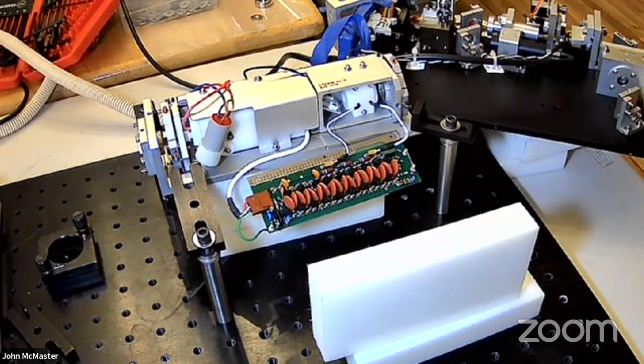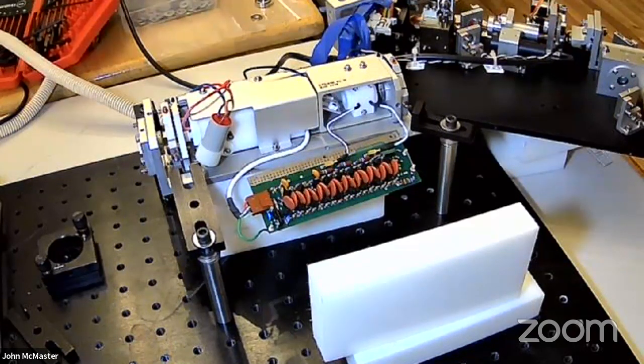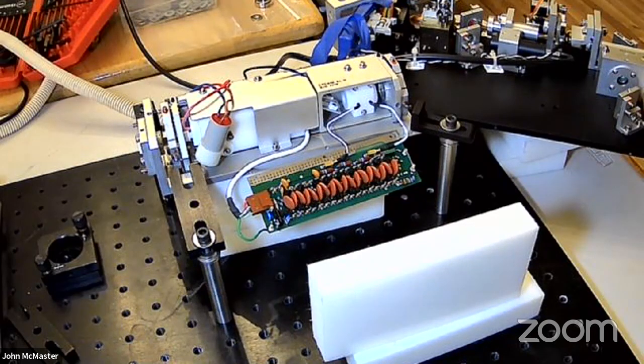Great. And so now the idea is if we were to just replace this one element, it's going to knock everything out of alignment. And there are so many optics in here that need to be aligned. It's going to be very hard to get everything, starting from that point, back to a working state. So it turns out to be easier to do this. Remember I said that we could operate this as just a very long pulse? The flash lamp is not being switched. It fires, the laser starts lasing, it outputs some light, and you get a very long pulse. Do you remember we talked about that earlier?